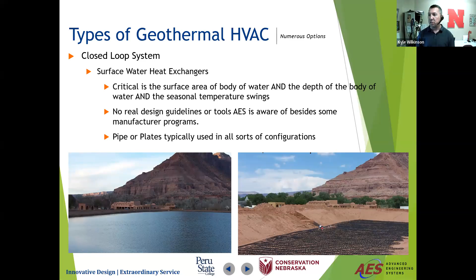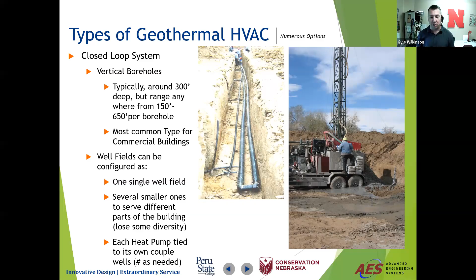Going back a slide, you can see it here: they drill the 6-inch hole, then put the pipe in the shape of a big U, add a weight and a rod, and force it all the way down. Then they fill the hole with thermal grout, which helps the energy go from the dirt into the pipe, because air is more of an insulator. If the hole just has pipes in it without grout, the energy won't transfer well from the dirt to the pipe. The grout forms that bridge so the energy can get into the pipe and back out into the ground.